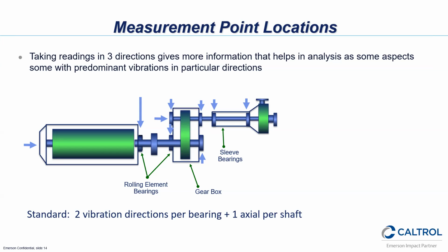We used to do this back in the day where we would have a single channel accelerometer, where you had to move to each of those positions on that one bearing. But now we have what's called a triaxial accelerometer. So you put that in the horizontal position and it collects a different spectrum for each direction, without having to move the accelerometer to those different positions. Plus it takes a 4th one, which is called PeakVue, which again, I'll get to a little bit further in the demonstration.